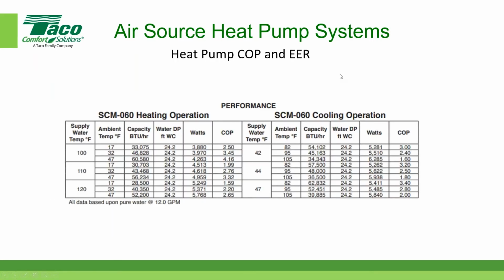I took these numbers directly off this chart, and if you'll notice, it's over here. With a supply water temperature of 42 degrees Fahrenheit, here's my capacity of 45,163, and there's my watts. I just did a calculation that showed you that the coefficient of performance was equal to 2.40 in this case. So this is the manufacturer's data, which I just calculated for you.